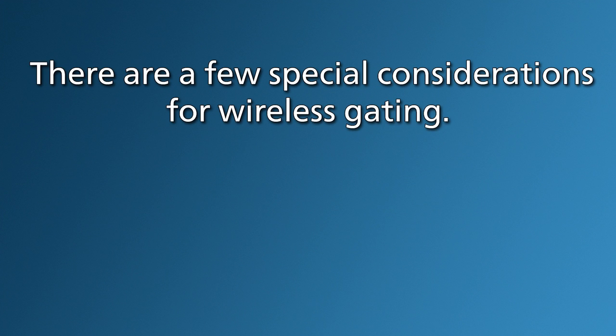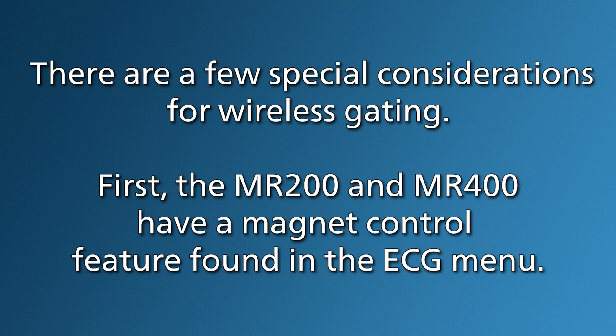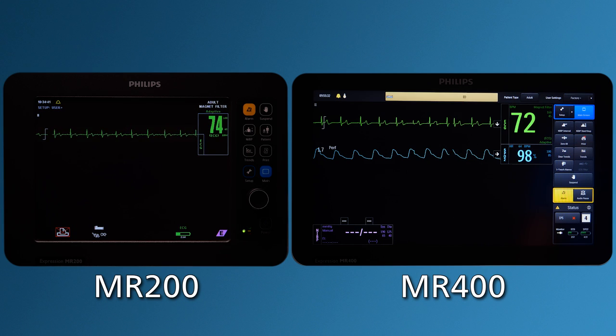There are a few special considerations for wireless gating. The MR200 and MR400 have a Magnet Control feature found in the ECG menu.